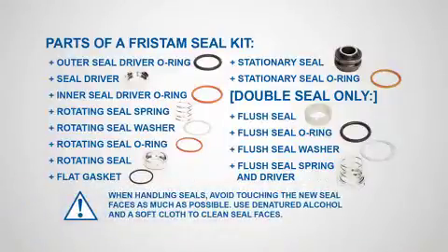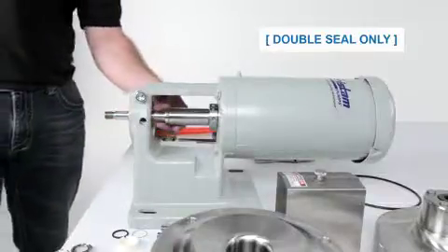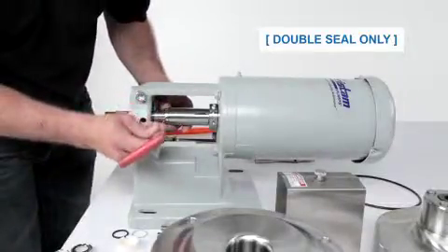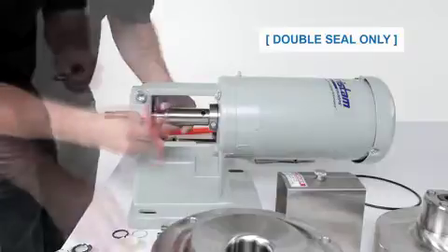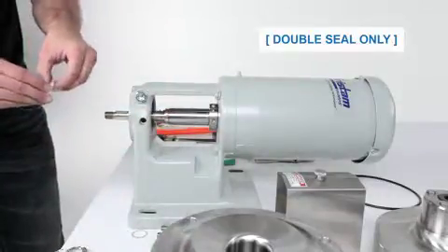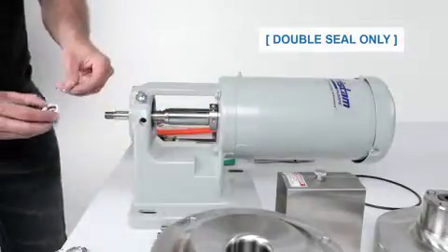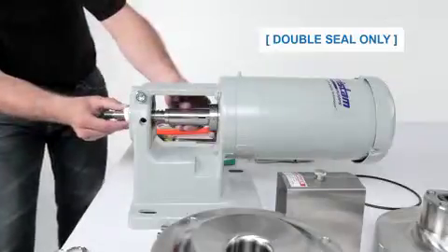When handling seals, avoid touching the new seal faces as much as possible. Use denatured alcohol and a soft cloth to clean seal faces. First, install the double seal components. This includes the rear seal driver and spring, the seal washer, the seal O-ring, and the flush seal.